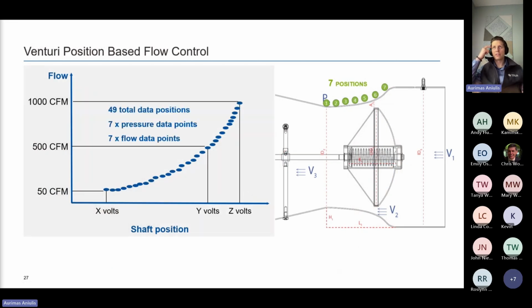Now, Venturi-based, position-based flow control requires some factory characterization in order to define what the CFMs are at the different positions. The industry standard is 7 positions and 7 pressures at each of those positions, giving you a total of 49 data positions, which are then linearized and dumped into our valve brain. And the way you would interface with it is with a simple scale, 0-10 in, 0-10 out.